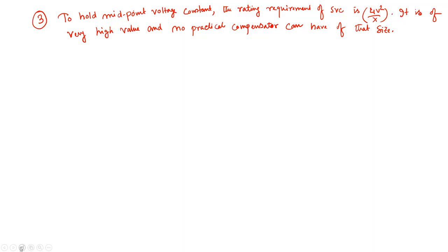Although there is an increase in power transfer capacity, it is not possible to achieve the theoretical maximum power transfer capacity even with a midpoint compensated line, because it requires a very huge amount of compensation or a very high rated compensator.